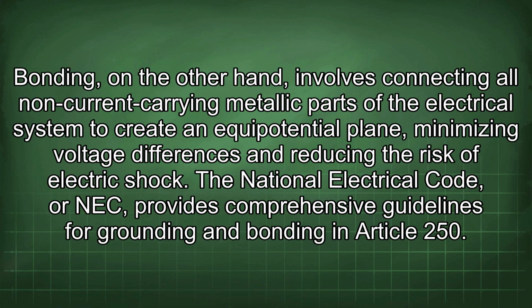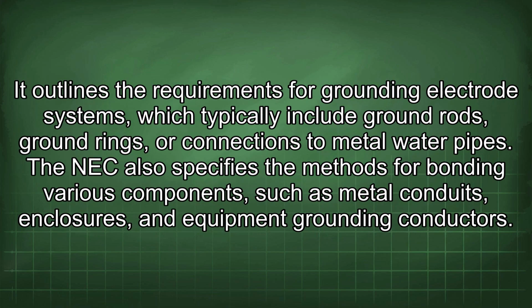Bonding, on the other hand, involves connecting all non-current carrying metallic parts of the electrical system to create an equipotential plane, minimizing voltage differences and reducing the risk of electric shock. The National Electrical Code, or NEC, provides comprehensive guidelines for grounding and bonding in Article 250. It outlines the requirements for grounding electrode systems, which typically include ground rods, ground rings, or connections to metal water pipes. The NEC also specifies the methods for bonding various components, such as metal conduits, enclosures, and equipment grounding conductors.